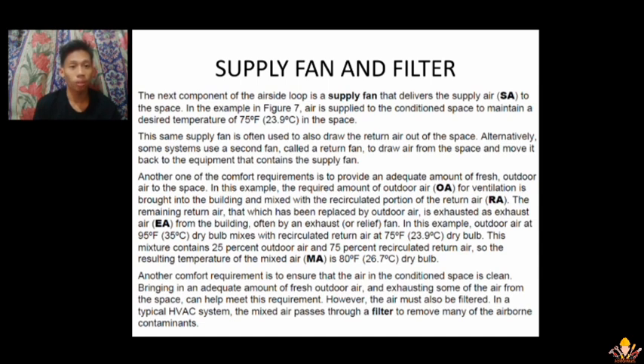Another one of the comfort requirements is to provide an adequate amount of fresh outdoor air to the space. In this example, the required amount of outdoor air for ventilation is brought into the building and mixed with the recirculated portion of the return air. The remaining return air, that which has been replaced by outdoor air, is exhausted from the building, often by an exhaust or relief fan. In this example, outdoor air at 95 degrees Fahrenheit dry bulb mixes with recirculated return air at 75 degrees Fahrenheit dry bulb. So the resulting temperature of the mixed air is 80 degrees Fahrenheit dry bulb.